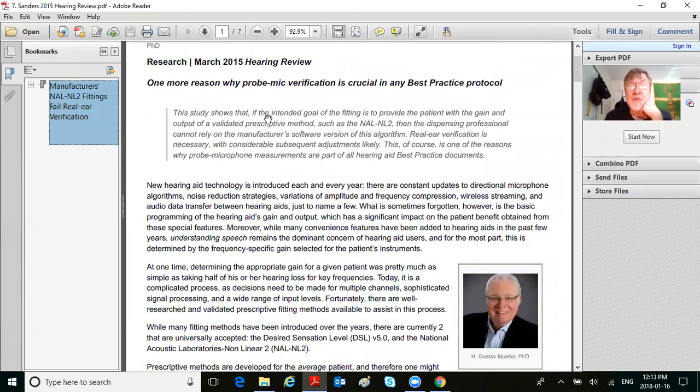This study shows that if the intended goal of fitting is to provide the patient with the gain and output of a validated prescriptive method such as NAL-NL2, then the dispensing professional cannot rely on the manufacturer's software version of this algorithm. Real ear verification is necessary, with considerable subsequent adjustments likely.